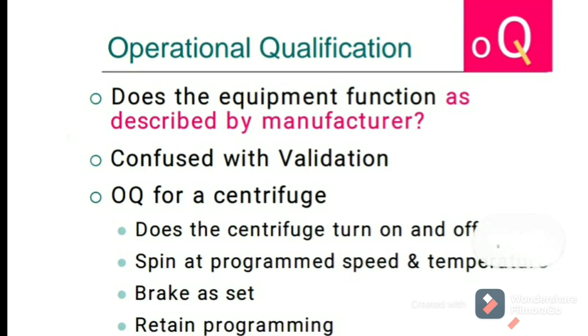Instrument calibration can be defined as the process of comparing the measurement made by the instrument to be calibrated against a standard, or an instrument known to be making measurements within acceptable limits of accuracy and precision. Usually calibration labs prefer a standard with 10 times the accuracy. However, most regulating organizations and authorities also accept a 3:1 accuracy ratio between two entities, one whose value has to be measured and the other, known as the standard, which is used as the reference for the comparison.